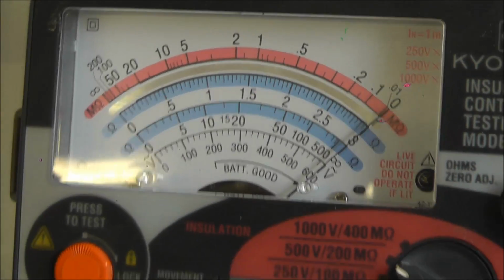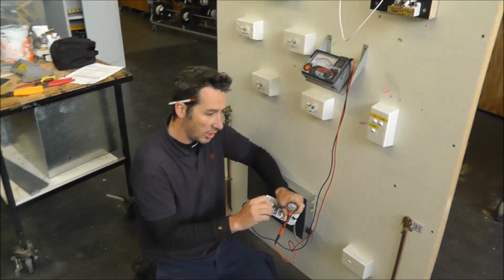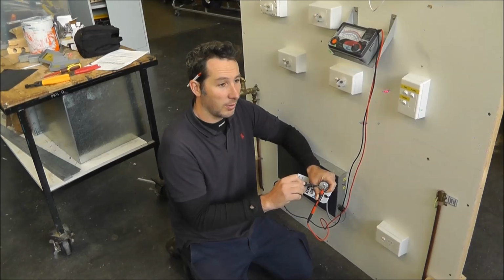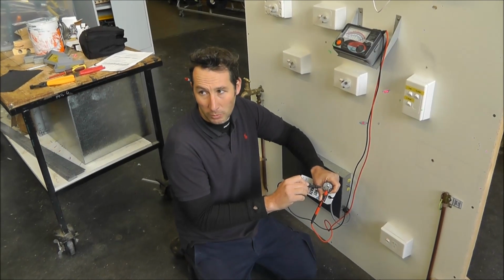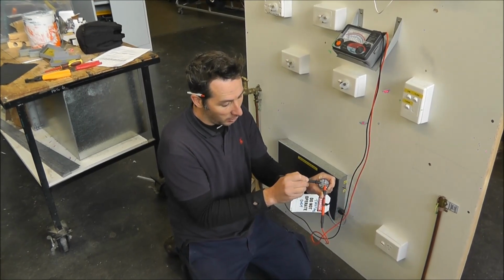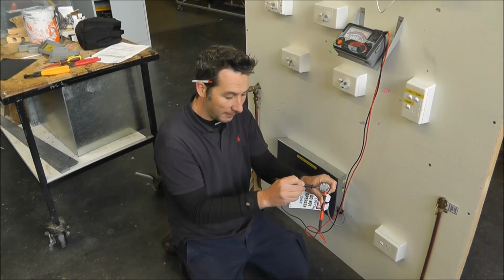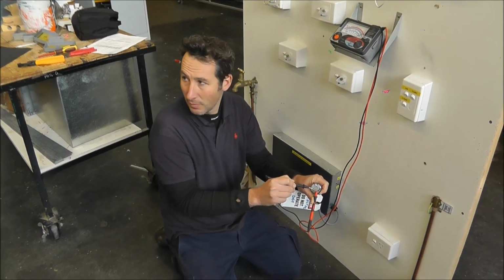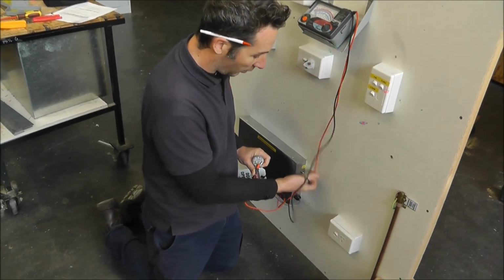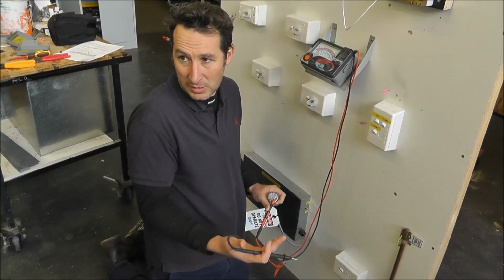Now, what you'd have to be careful of here would be that if it's a sheath heating element, the difference between 0 and 0.01 is very small. So you'd have to make sure, going from here, Bill, to touch them together to make sure that 0 is 0, and then seeing if it's actually any different when you go to there. And then the switch is on. If there's a fault, obviously with the switch off, it's just a dead short. It's a fail no matter what, isn't it?